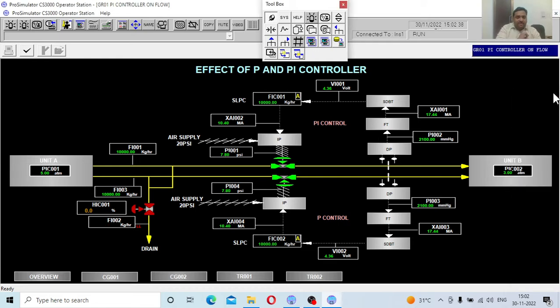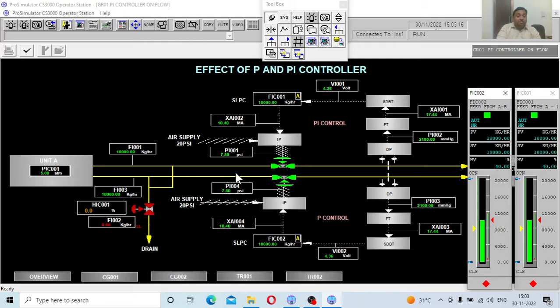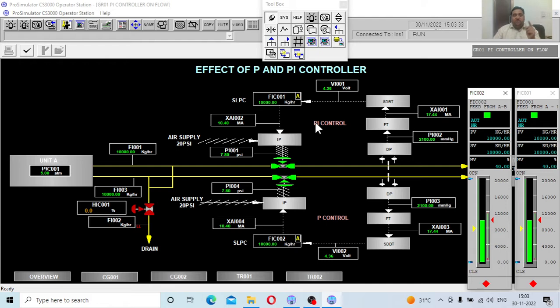The job of a controller is to reach the set point. We have two controllers: FIC001 which is the PI controller, and FIC002 which is the P controller. In both controllers the present set value is 10000, which is the flow happening in both lines at 10000 kg per hour. Now I will disturb the system using a third valve — opening HIC to 10 percent — which will disturb the flow in both lines. We will observe whether the process value reaches the set point despite the disturbance or not. Let us observe the disturbance problem first.